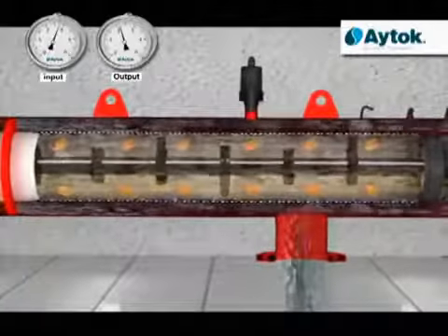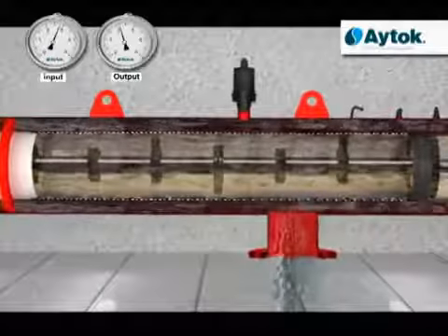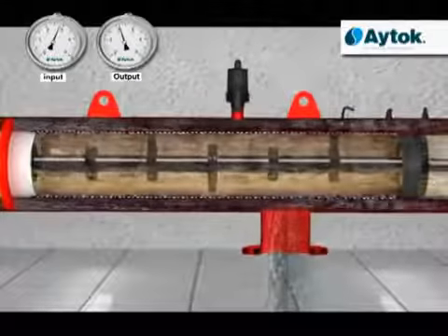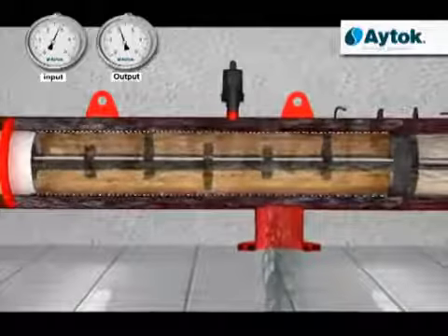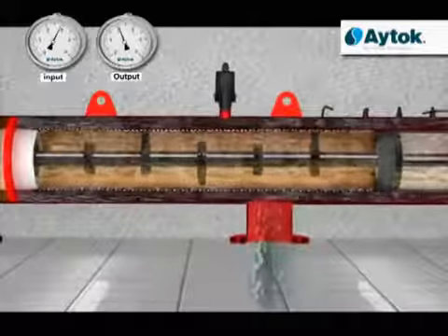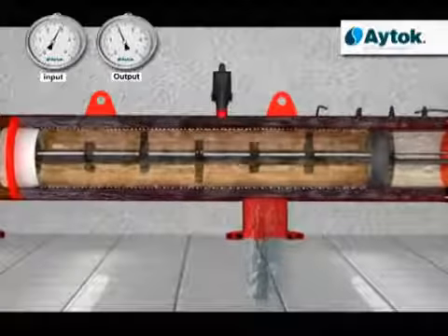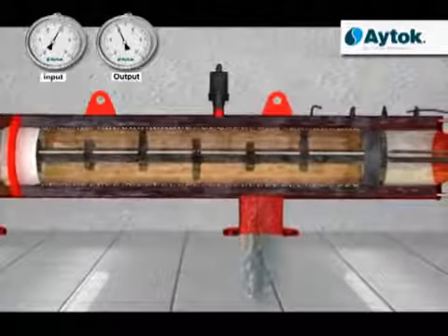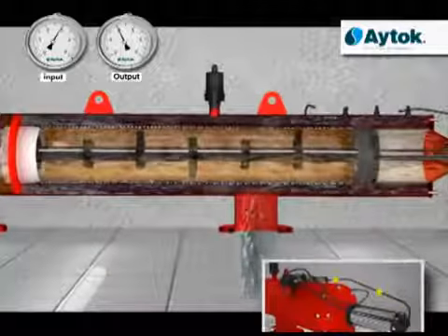The particles in the water that goes to exit from the internal part of the fine sieve, which is protected by a tough and spaced sieve, constitute a dirty layer on the inner surface of the filter. When the pressure arising from the layer reaches previously determined values, a backwashing operation starts for cleaning the fine sieve.